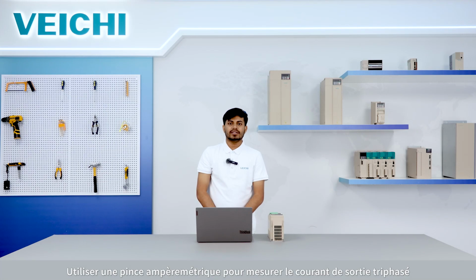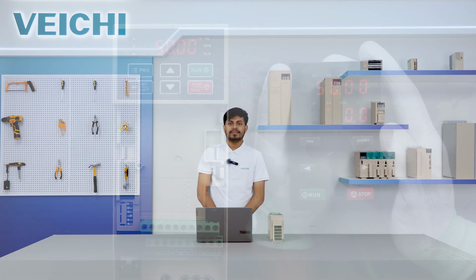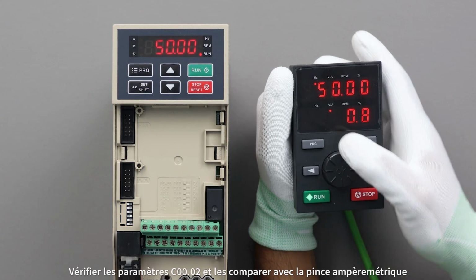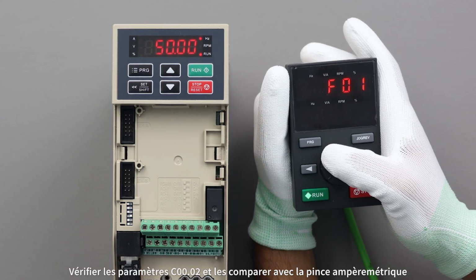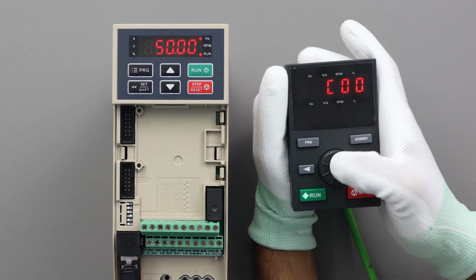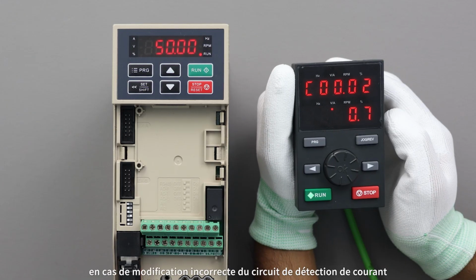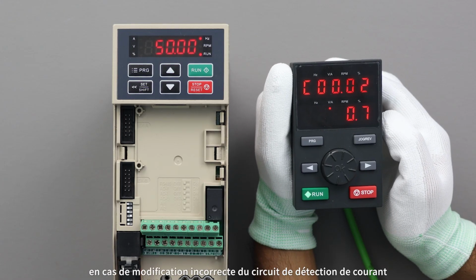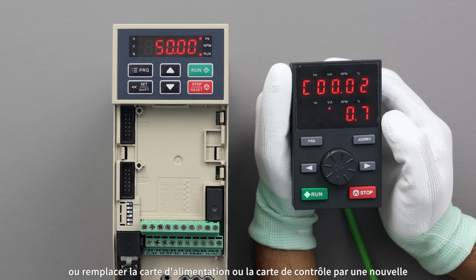Compare output currents. Use a current clamp meter to measure the three-phase output current. Ensure all phases currents are balanced. Check the C00.02 parameters and compare with the clamp meter. If incorrect, change the current detection circuit or replace a new power supply board or control board.